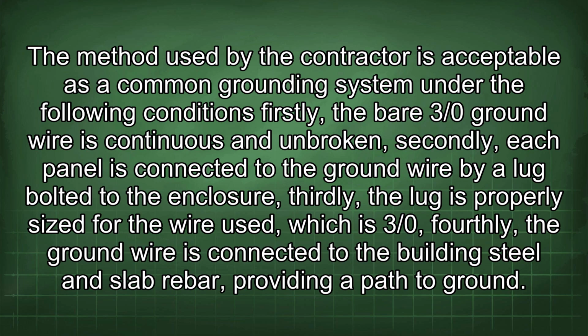Firstly, the bare 3/0 ground wire is continuous and unbroken. Secondly, each panel is connected to the ground wire by a lug bolted to the enclosure. Thirdly, the lug is properly sized for the wire used, which is 3/0. Fourthly, the ground wire is connected to the building steel and slab rebar, providing a path to ground.